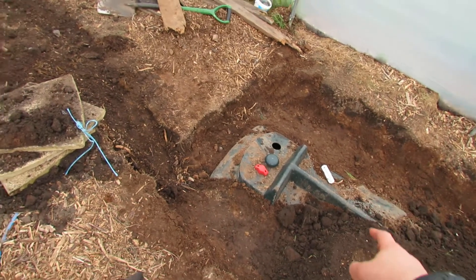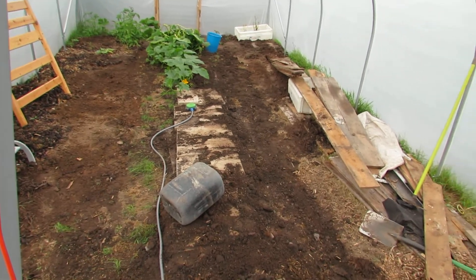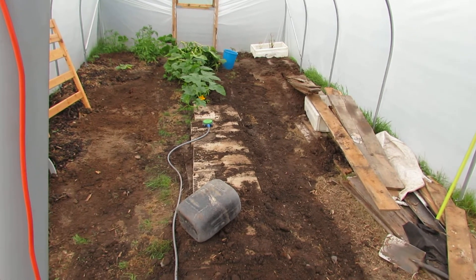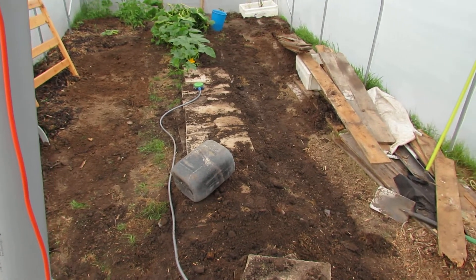The fan's pretty good. There's decent airflow coming out the pipe, considering it's 25 meters long and it's perforated and it's corrugated. I'm quite happy with that. But the temperature is only 15 coming out the end and the temperature going in is up to 30 — that's a good sign and a bad sign. It shows that the thermal store is definitely big enough; there's enough surface area to exchange that heat, as we're losing all of that heat by the time it gets to the end, which is good.